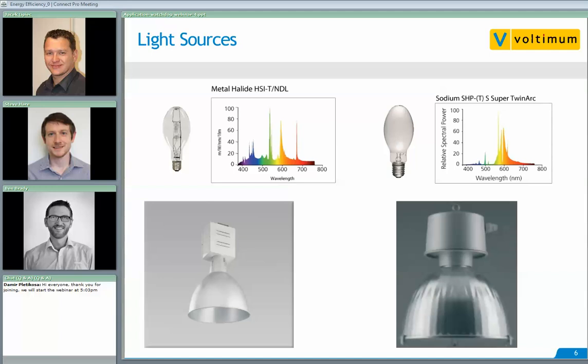The spectral power density graphs show the wavelengths of each lamp and a representation of what the high bay may look like that accommodates these lamps. This is probably the most common type of high bay that people have seen. It's important to note that in a sodium lamp, its peak wavelength is in the yellow or orange, giving it poor color rendering — generally bad news for any type of manufacturing or warehouse application where being able to reproduce a color accurately is important.